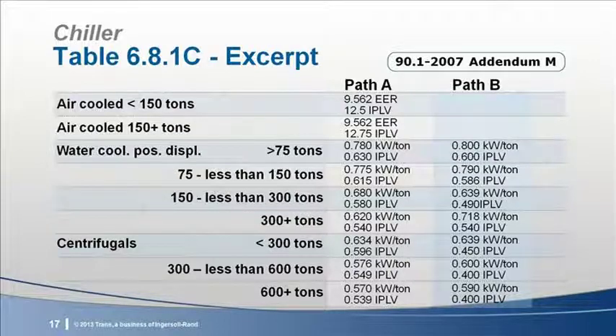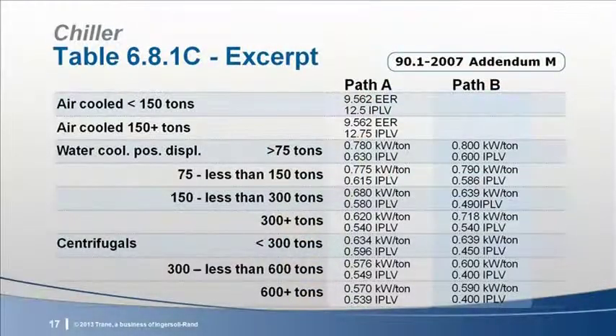Project teams can choose either Path A or Path B. Once the path is chosen, both the full load and IPLV requirements must be met. Another thing to note is that these requirements are in the mandatory portion of the standard, so they must be met for every chiller, whether the prescriptive or performance method of compliance is chosen. Looking at the chiller requirements compared to Path A, the Path B values are about 2 to 4% less stringent at full load, but have a more stringent IPLV.